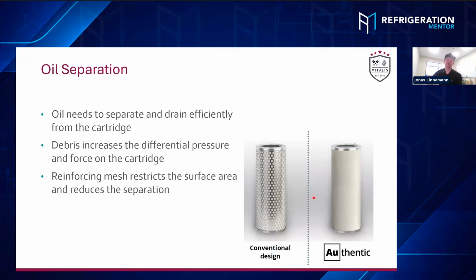One very obvious thing you probably notice here is that this reinforcement mesh at the outside of the cartridge surface is again restricting the flow rate of the CO₂. And by that, you actually accelerate the CO₂ flow in these little tiny holes. What you actually want to achieve is that the oil can easily flow down and separate. But by accelerating the flow at the outside of this reinforcement mesh, you just shoot a lot of drops back out of that cartridge, and then it travels out into the system. So that's why we designed this special cartridge here without an outer mesh. We made sure that we used the right components and the right meshes, which last for those high differential pressures and the higher forces, but do not restrict the oil separation.